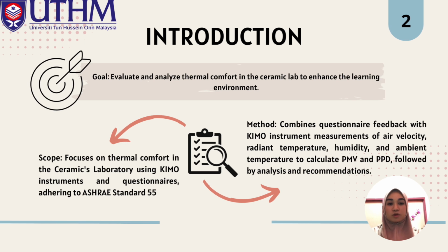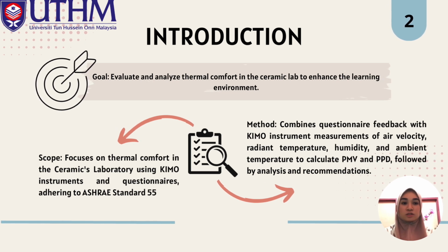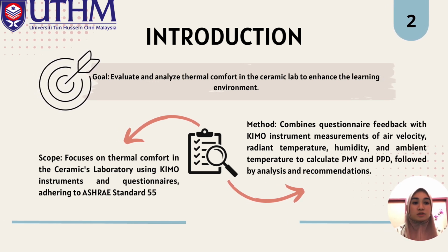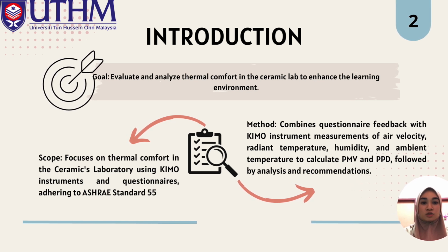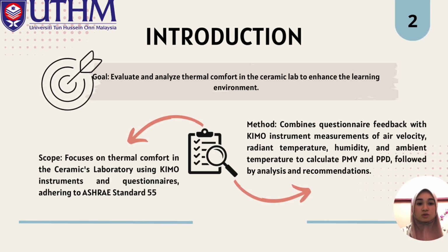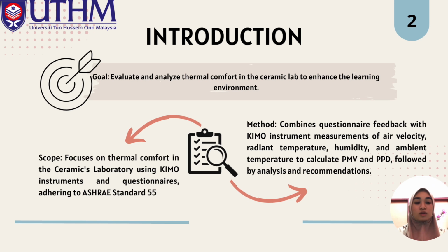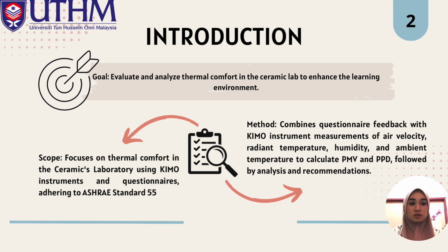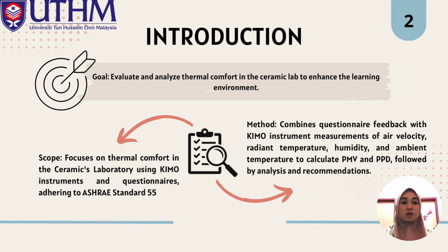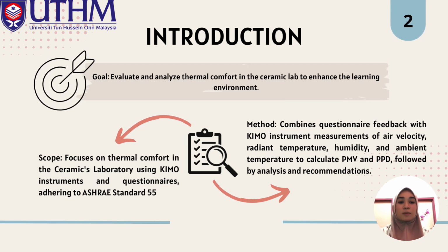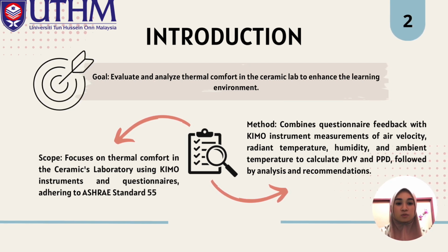For our scope of assessment, we focus on thermal comfort in the ceramic laboratory using KIMO instrument and questionnaire, adhering to ASHRAE Standard 55. For our description of assessment, our method combines questionnaire feedback with KIMO instrument measurements of air velocity, radiant temperature, humidity, and ambient temperature to calculate PMV and PPD, followed by analysis and recommendations.